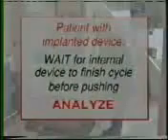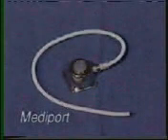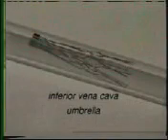If the internal device is delivering a shock to the patient, wait for this cycle of shocks to finish before pushing the Analyze button on the ZOLL. Remember to tell the CPR team about the presence of any implanted devices. It is important to check the function of implanted devices after defibrillation. Other implanted devices, such as a Mediport or an inferior vena cava umbrella, will not interfere with the function of the ZOLL 2000, and these devices are not known to be affected by defibrillation.